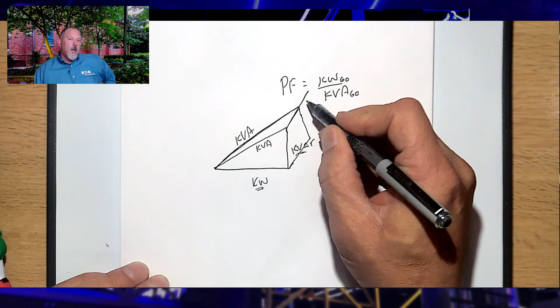This kVA includes harmonics, so the more harmonics you have, the bigger your kVA gets—exactly what you said. Your kilowatts didn't change, because harmonics don't affect kilowatts. But if your kVA is bigger, what does that make your power factor? Smaller. So the more harmonics you have, the worse your power factor will be, in terms of what's called total power factor, TPF.